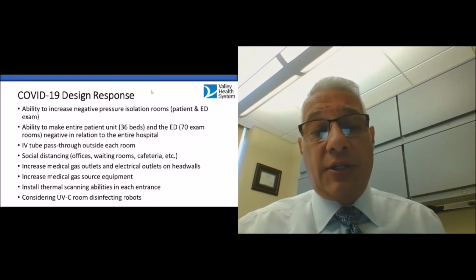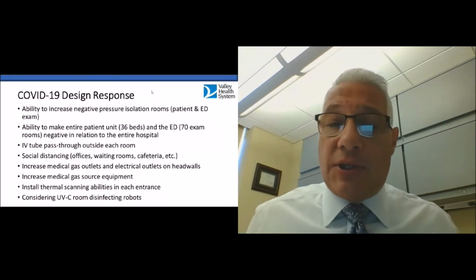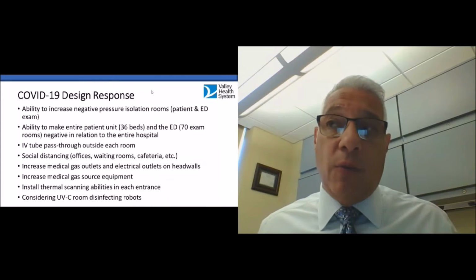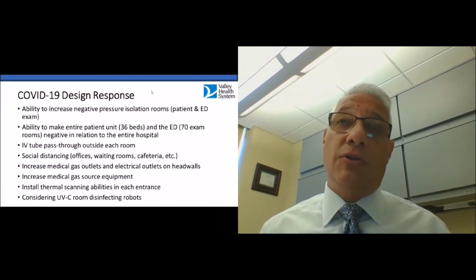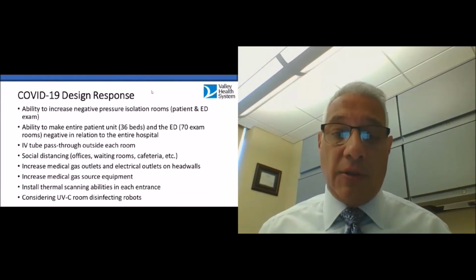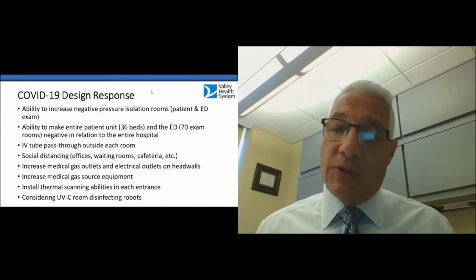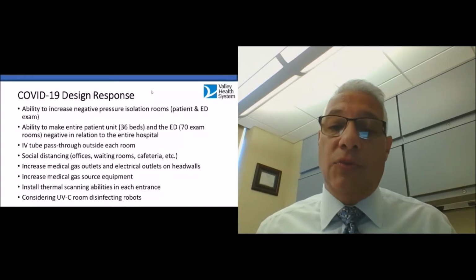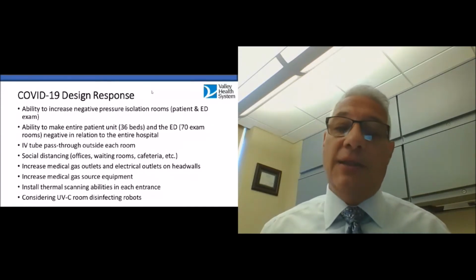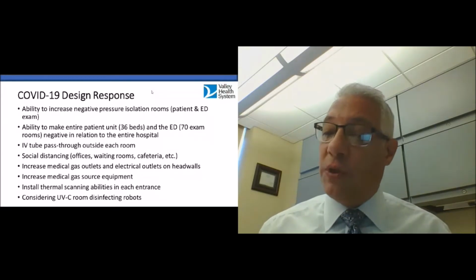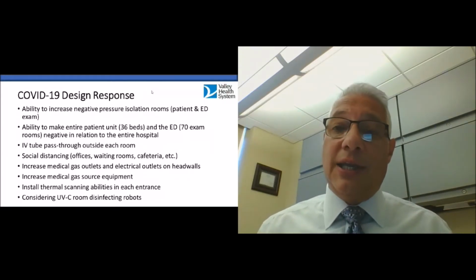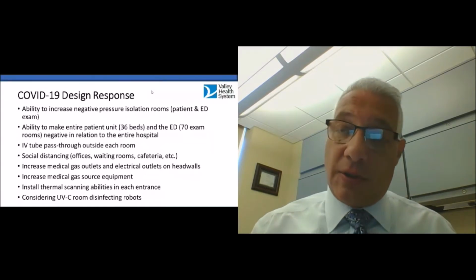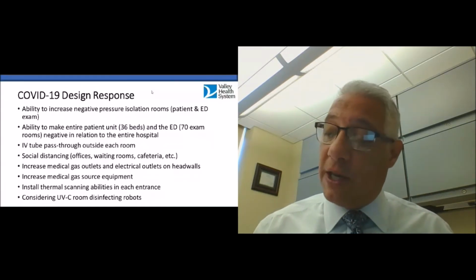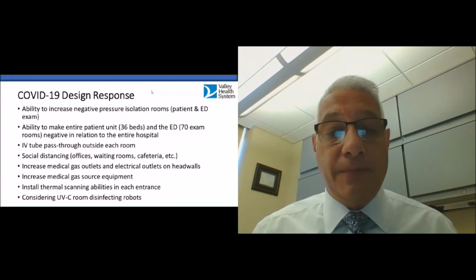We have increased medical gas outlets and electrical outlets on all our head walls. So all of our head walls are similar to critical care head walls. We have double the amount of med gas and emergency and normal outlets throughout the whole hospital. That's meant to be for, should we have another surge, the need for medical air, or oxygen, or medical vacuum will be there.